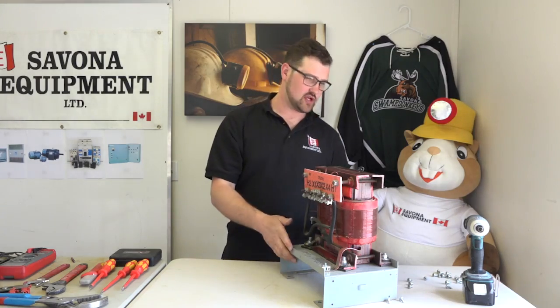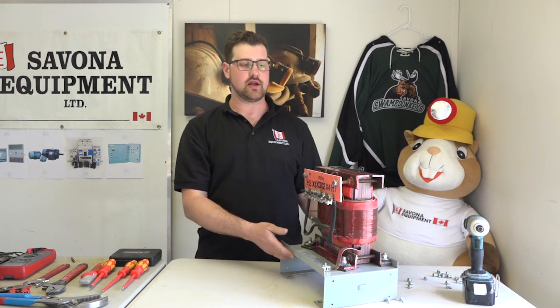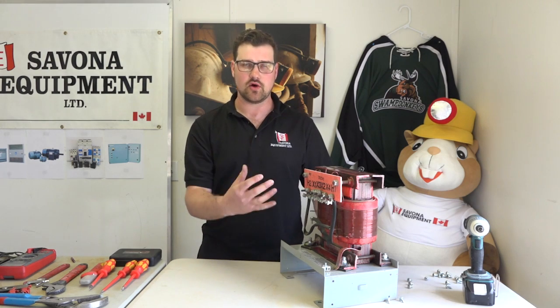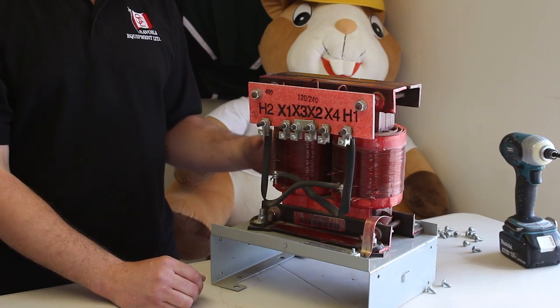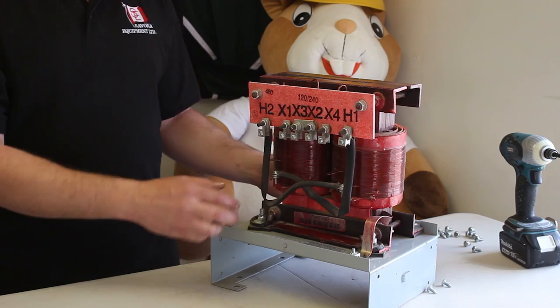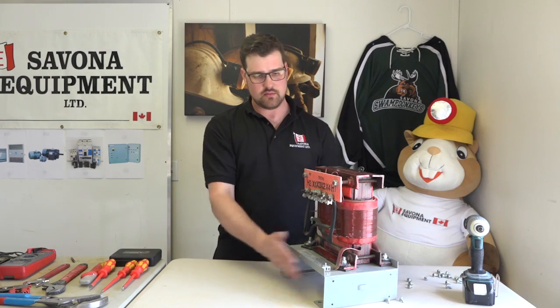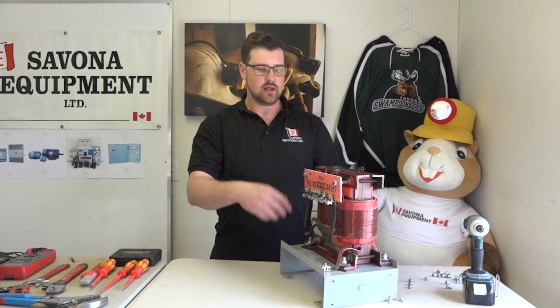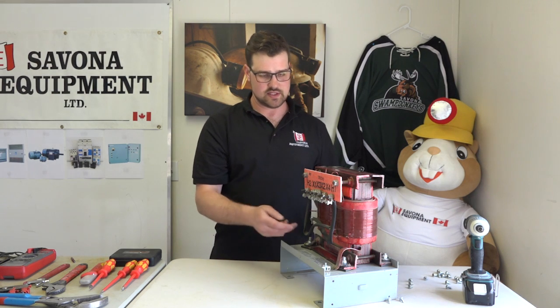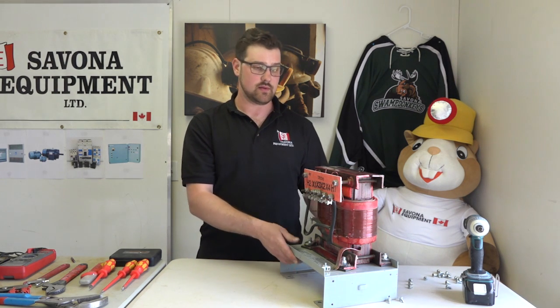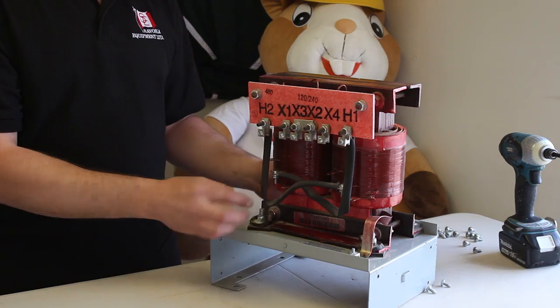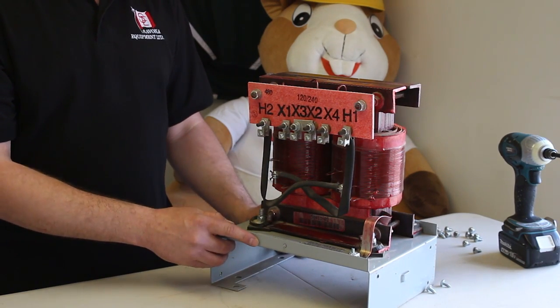So I took the covers off just so we can have a better look at a transformer and what it's made of. When you're testing a transformer, you don't necessarily have to take all the covers off like that. Some transformers won't let you take all the covers off. Most of them come on a simple base like this, and then they have the covers around them so that if there is ever something that goes wrong with your transformer, it's easy to take it out and have it serviced or rewound.